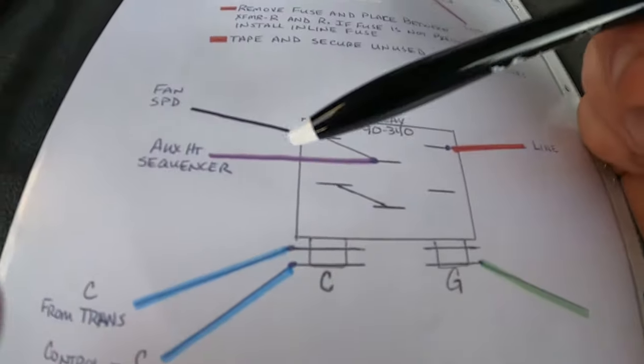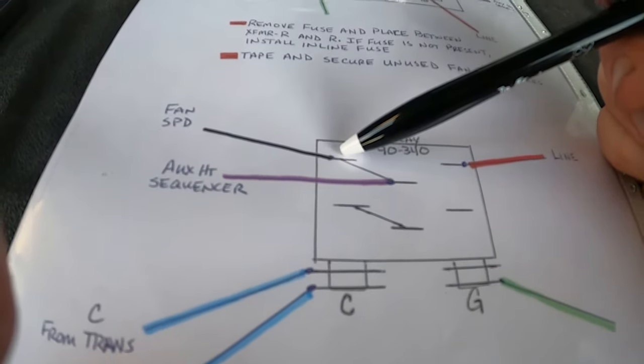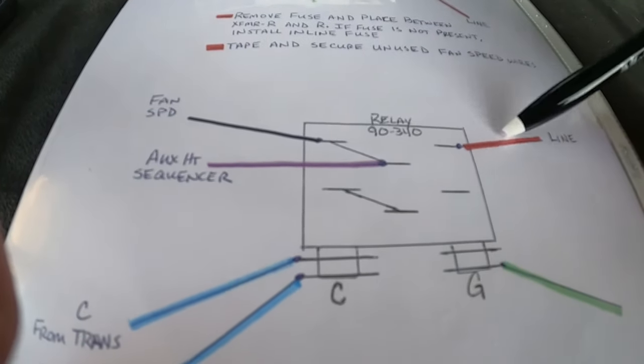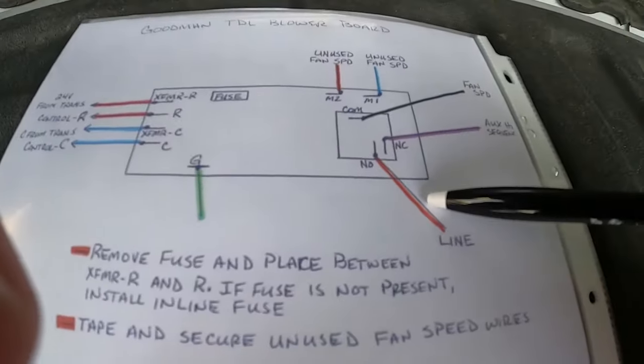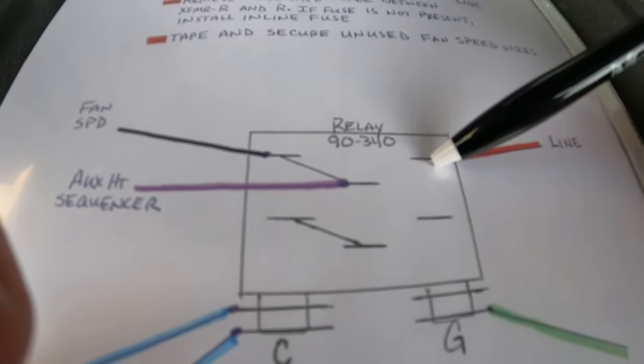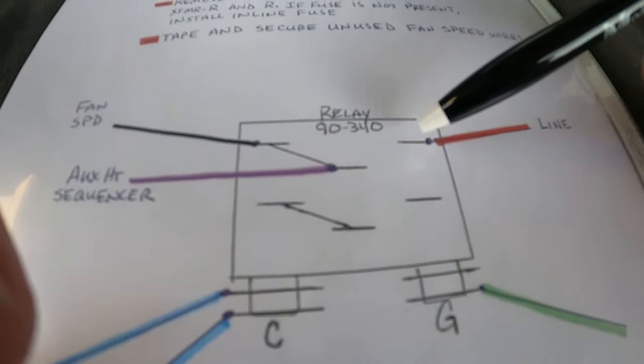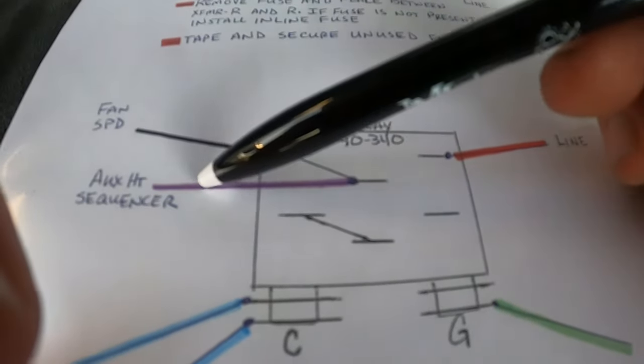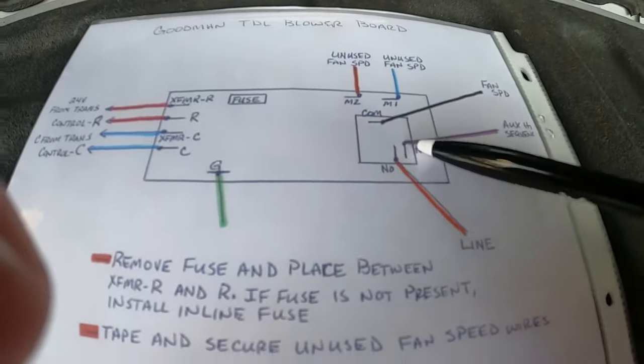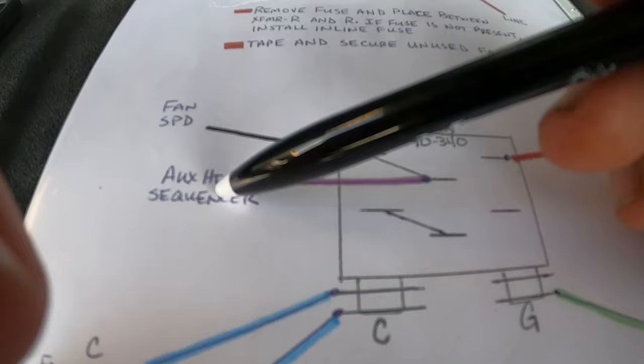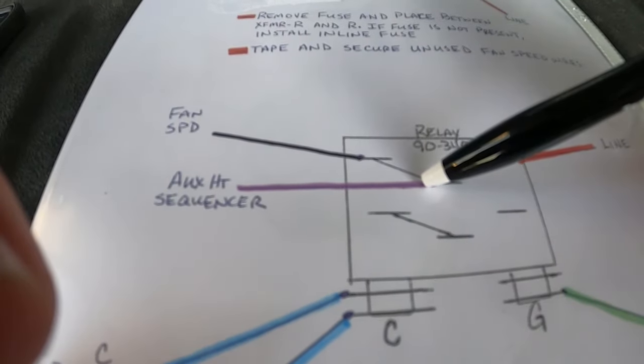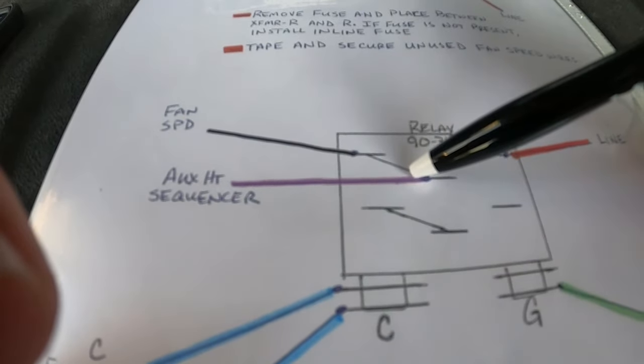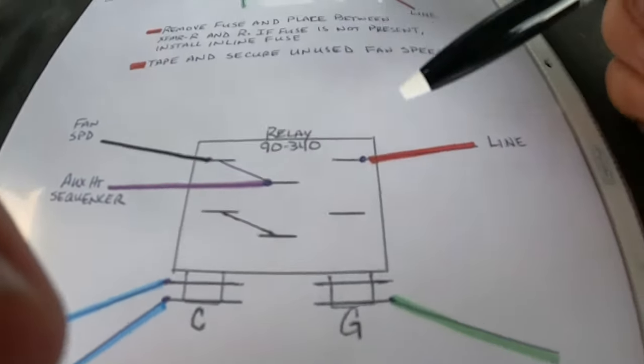Bring your blower speed to your common terminal. Bring your line voltage in, this one, to your top right normally open terminal, and this is the one that's going to be your back feed from your heat strip sequencer. So if the heat strips call and that thing closes, it's going to energize the heat strips, and then it's going to come back here, energize your blower motor.